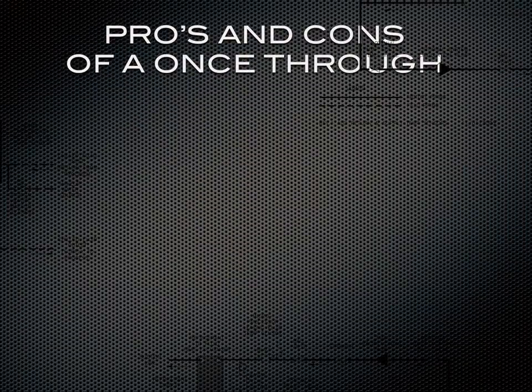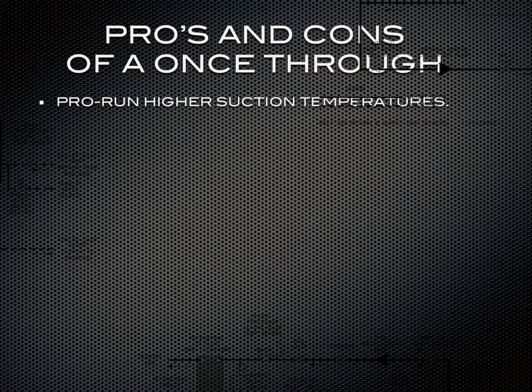Let's go over the pros and cons of a once-through chiller. The first pro is that you can run higher suction temperatures. Suction temperature is the temperature of your refrigerant. The lower suction refrigerant temperatures you have, the less capacity on your chiller. The higher suction temperatures that you have, the more capacity that you'll gain out of a chiller. For example, if you have 55 degree F returning to your chiller evaporator directly, and you need 45 degrees going back out to your process, you can do this with 40 degree suction temperature. And you can only have a 5 degree temperature difference between the suction and the desired leaving process water.